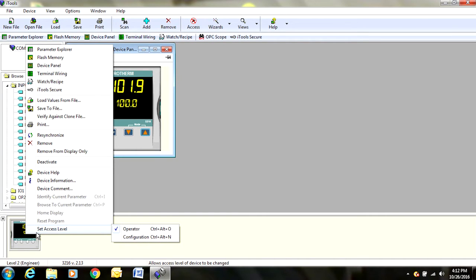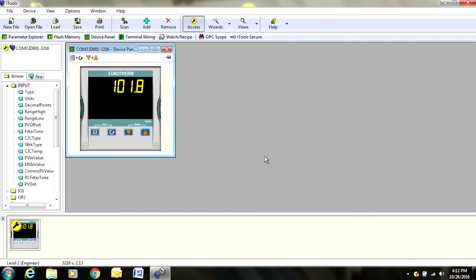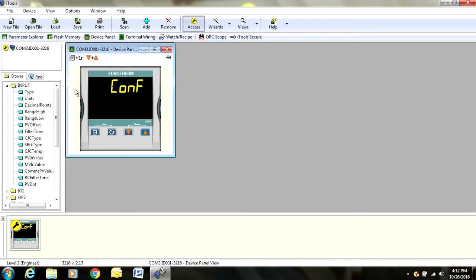We can change it from operator mode to configuration mode. We are going to right click down here, come to set access level, where it says operator, we are going to switch it to configuration. Once here, it is going to lock out the controller on the face of the calibrator so we won't be able to change anything. That is OK. We will go back in just a minute. We will hit yes. Once here, it changes to configuration, reminding you that nothing is actually working right now and it may cool down a little.